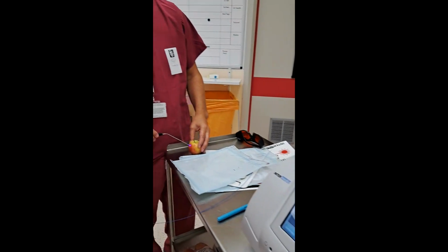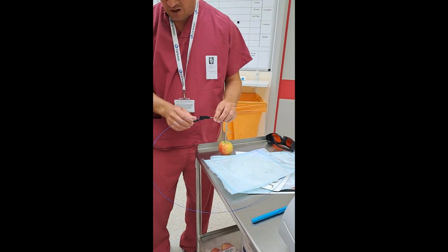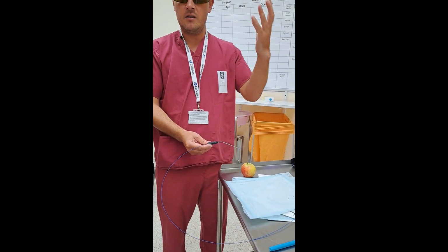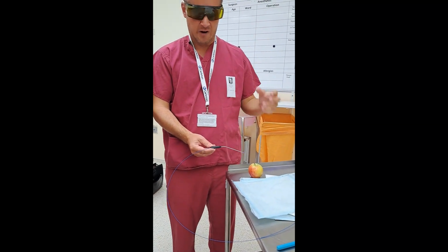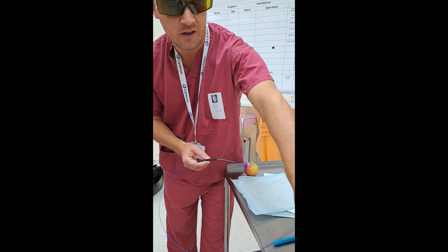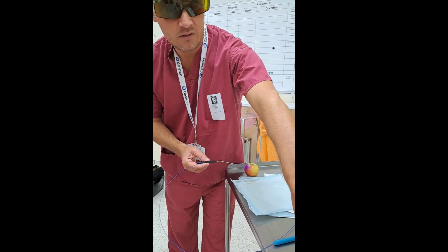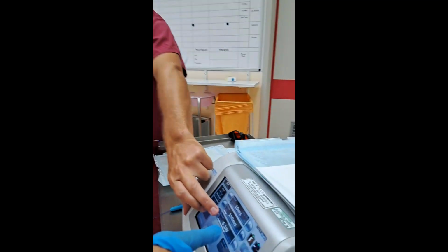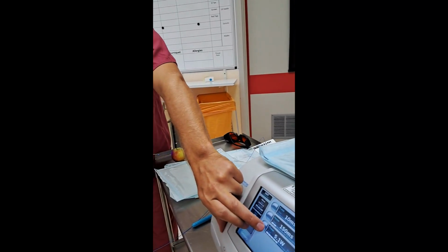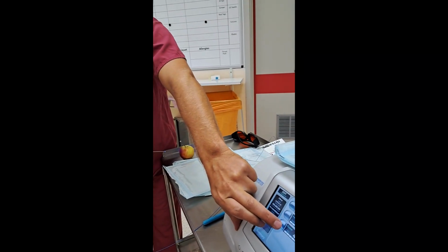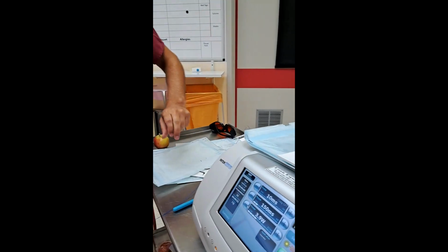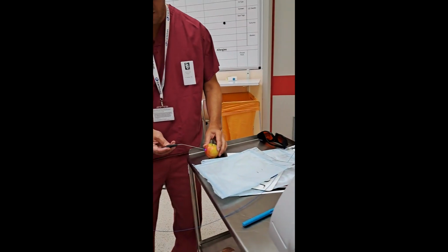So that's our red aiming beam. This one has slightly higher absorption in oxyhemoglobin, so in red, but 10 watts is quite high, so we'll put that down. And as we said, this is the time, so we have the time for the pulse itself and the time for the relaxation, so the time between each pulse. Leave it at 4 and you can see something a bit punchier than the other one.